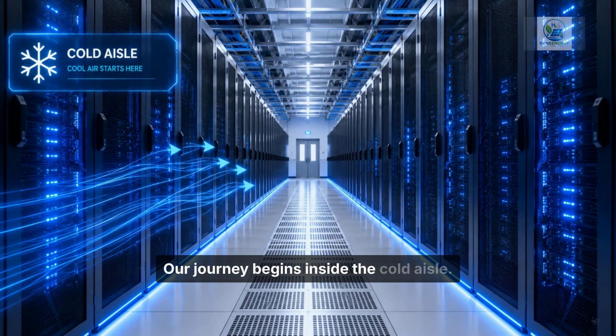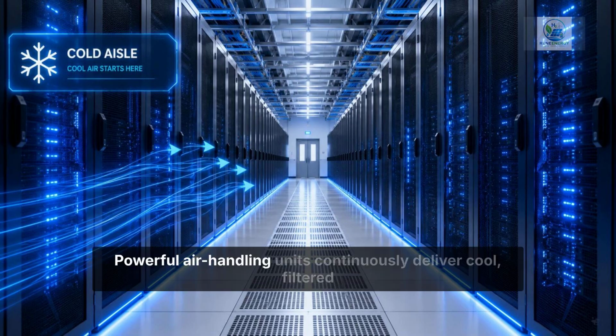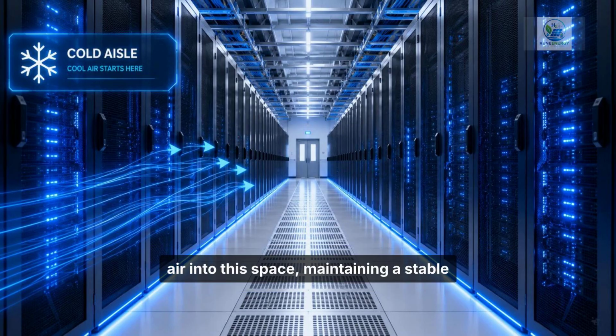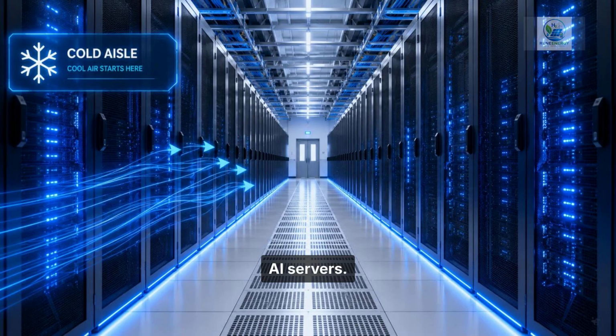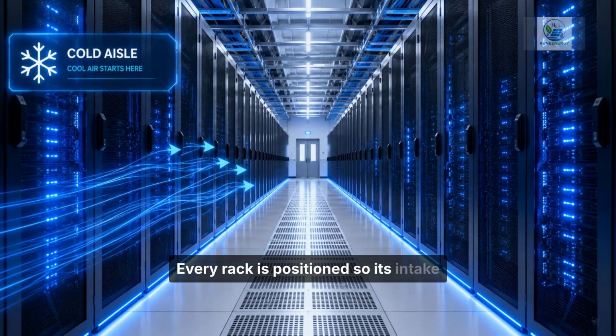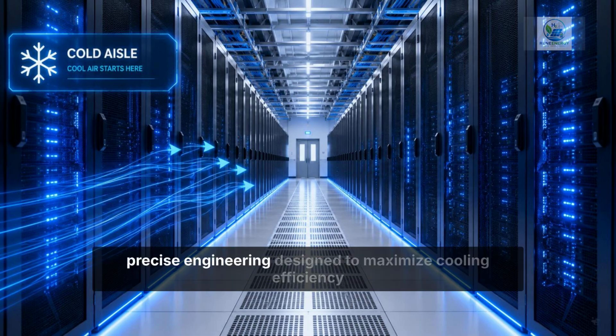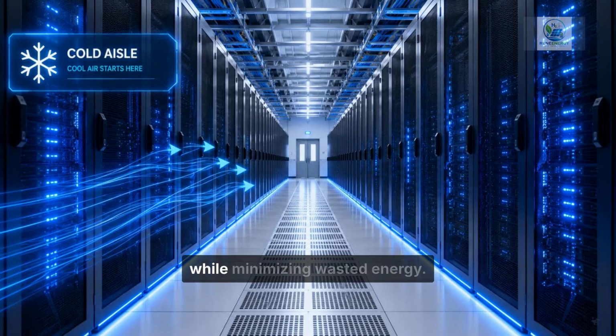Our journey begins inside the cold aisle. This carefully engineered corridor is where chilled air first enters the server room. Powerful air handling units continuously deliver cool, filtered air into this space, maintaining a stable environment for thousands of AI servers. Every rack is positioned so its intake faces the cold aisle, ensuring each processor receives the coolest possible air. This isn't accidental. It is the result of precise engineering designed to maximize cooling efficiency while minimizing wasted energy. Here, the invisible battle against heat truly begins.